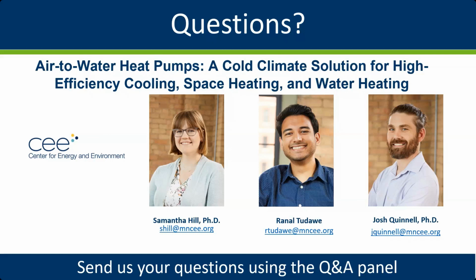Thank you, Sam. Jumping to our next question. Pat asked, if a current in-slab hydronic system is working well, being supplied by a high efficiency propane domestic hot water heater and a flat plate heat exchanger, could a domestic hot water heat pump replace the propane hot water heater, or could that possibly work? Or is a split type system likely needed?